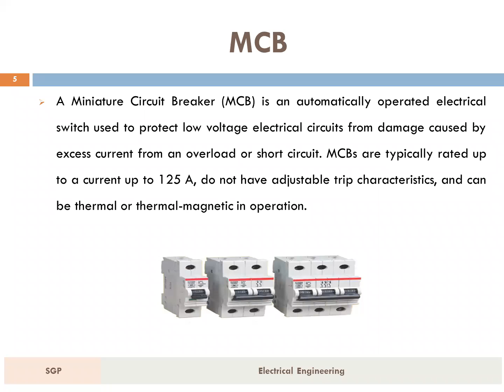Now we are going to see the working of MCB. There are two arrangements for the operation of a miniature circuit breaker: one due to the thermal effect of overcurrent and the other due to the electromagnetic effect of overcurrent. The thermal operation of the MCB is achieved with a bimetallic strip whenever continuous overcurrent flows through the MCB. The bimetallic strip is heated and deflected by bending. The deflection of the bimetallic strip releases a mechanical latch. As the mechanical latch is attached to the operating mechanism, it causes the MCB contacts to open.